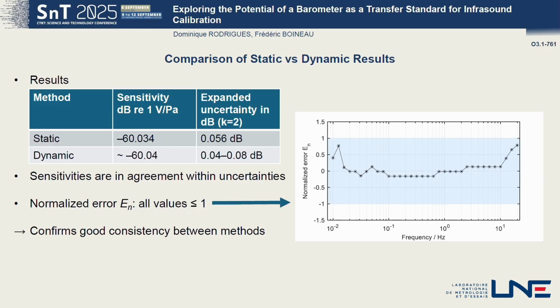Okay, so this slide is the comparison between the static and dynamic results. As a reminder, you have here the results for the static and dynamic methods with the uncertainties. The sensitivities seem to be in good agreement within the uncertainties, but to check this more formally, we look at the normalized error. The normalized error is a classical performance criterion used to conclude on the consistency of bilateral comparisons. The satisfactory range is that the normalized error must be below unity to conclude consistency between the results. You have here the normalized error as a function of the frequency, and as you can see, all the values respect this: the normalized errors are below unity, so we can conclude on the consistency between the results of the static and the dynamic method.